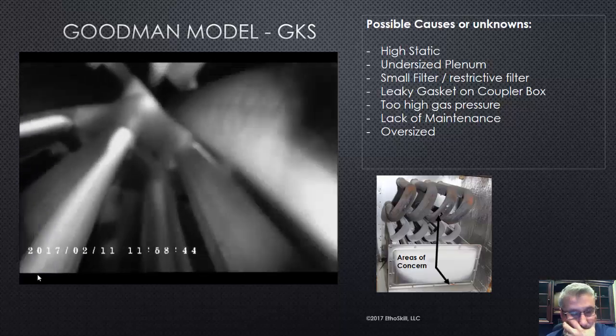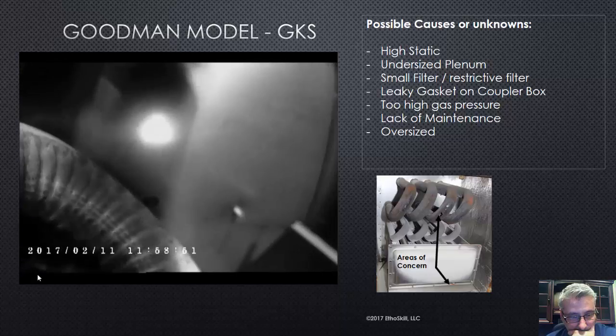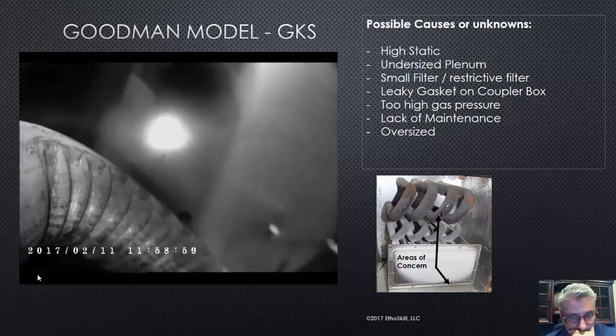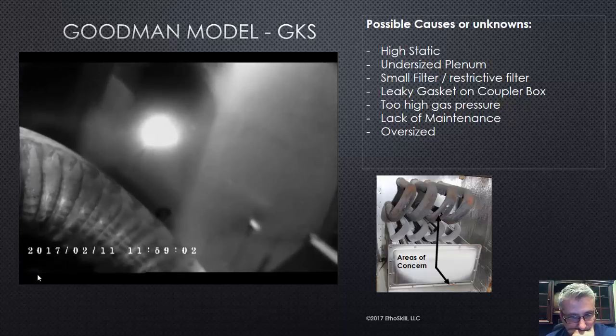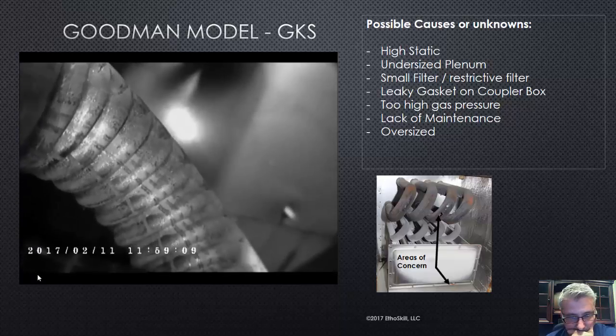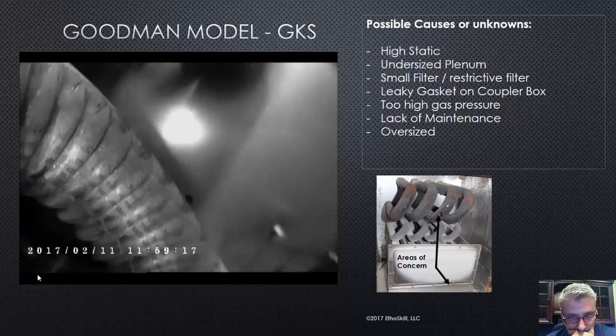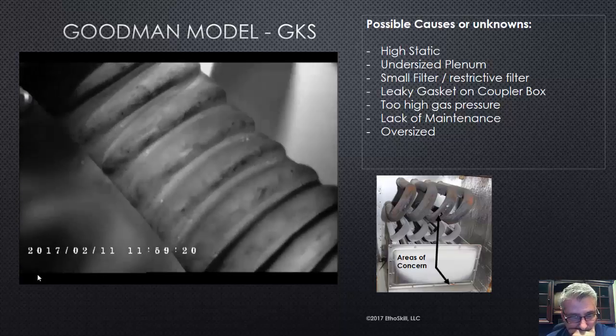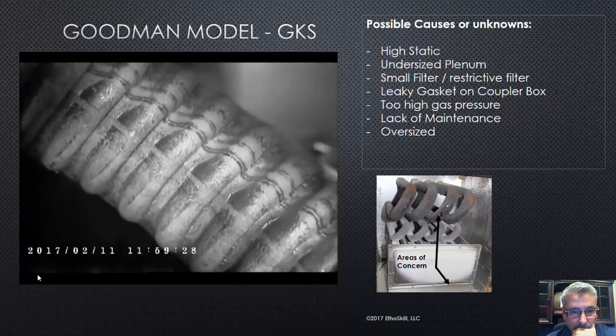If there's any pitting or holes that you find down in this lower section, here's what's going to happen. What we teach at RapidTech is that all condensing gas furnaces with an induced draft or vent motor assembly — these are really vent motors pushing the exhaust out, not true induced draft. So this entire primary heat exchanger is under negative pressure. If we start to draw air in through any holes, you're going to find them down in here. The reason that's happening is you're getting condensation in the primary — and any time you condense in a primary, that's bad. So if you're drawing air in there, you could get something like this to happen.